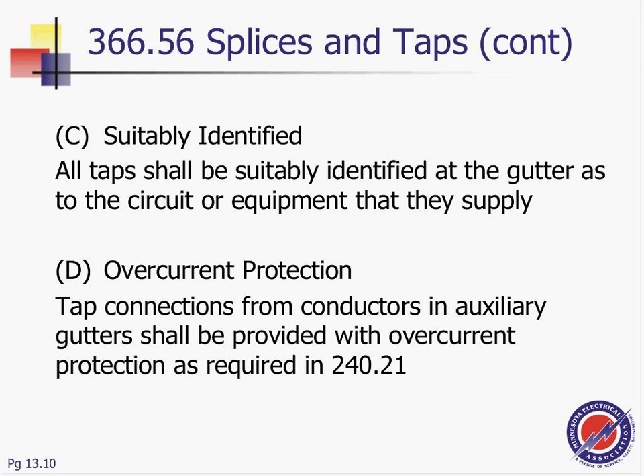Taps shall be suitably identified at the gutter as to the circuit or equipment that they supply. Tap conductors from conductors in the gutter shall be provided with an overcurrent protection device. So you have to protect your tap conductors from the gutter with an overcurrent protection device. Splices and taps shall be permitted within gutters where they are accessible.